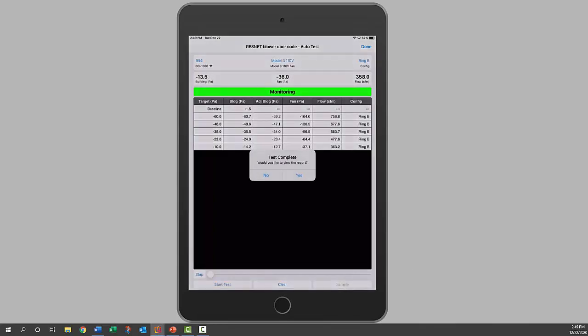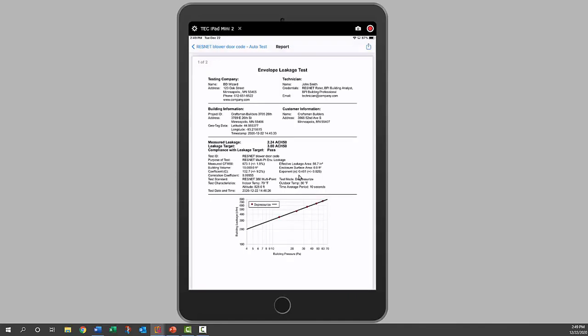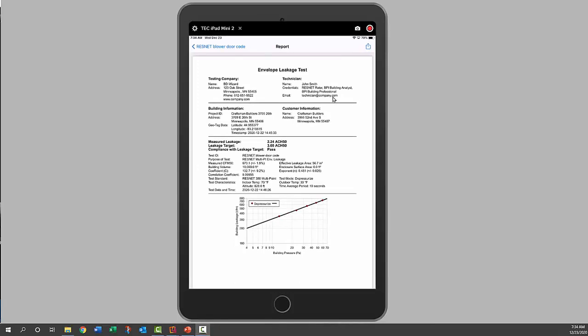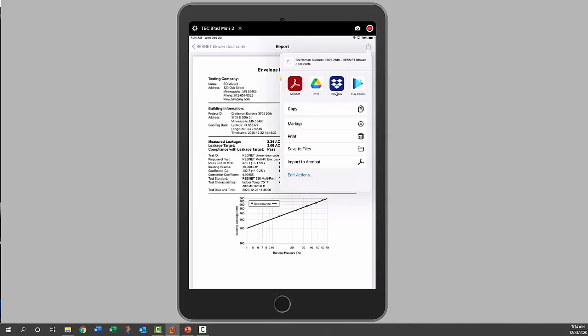Our test is all done, so we'll click yes, we'd like to see our report. We can see our leakage target is three, we're at 2.24 air changes per hour, so it passes. It also has our CFM 50 number here and additional information besides all of our data.